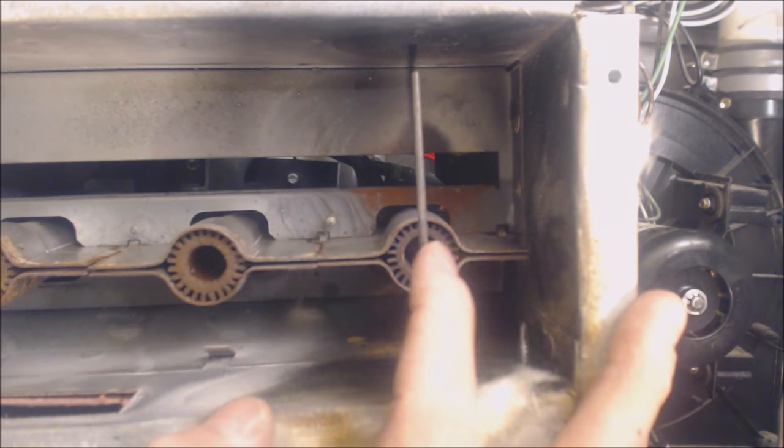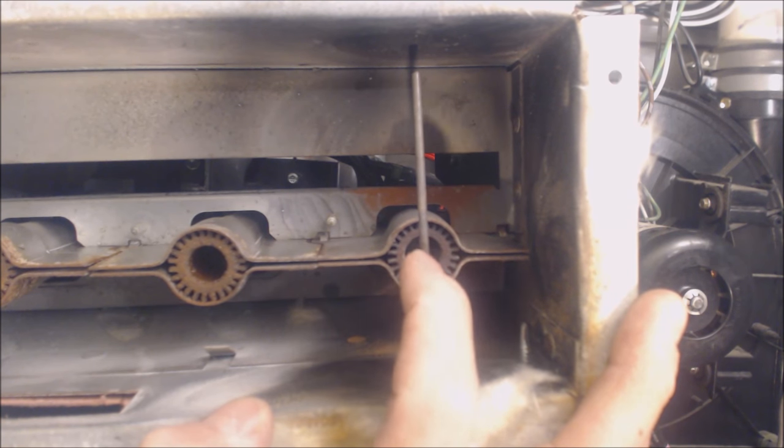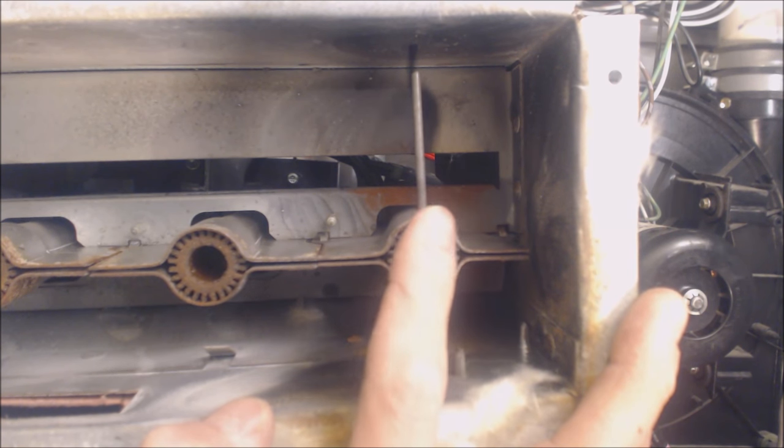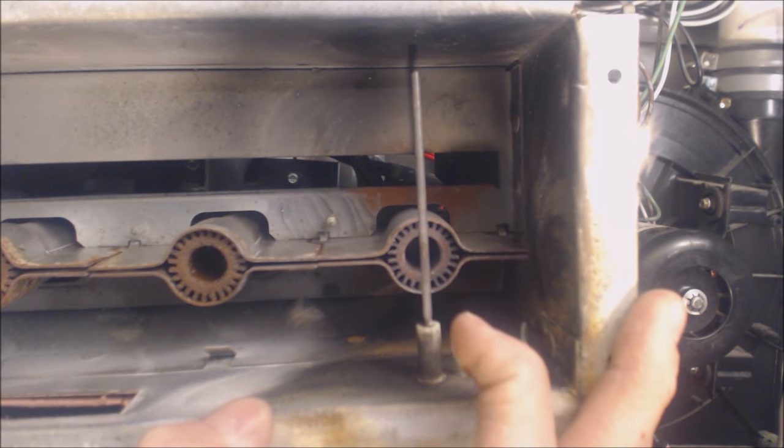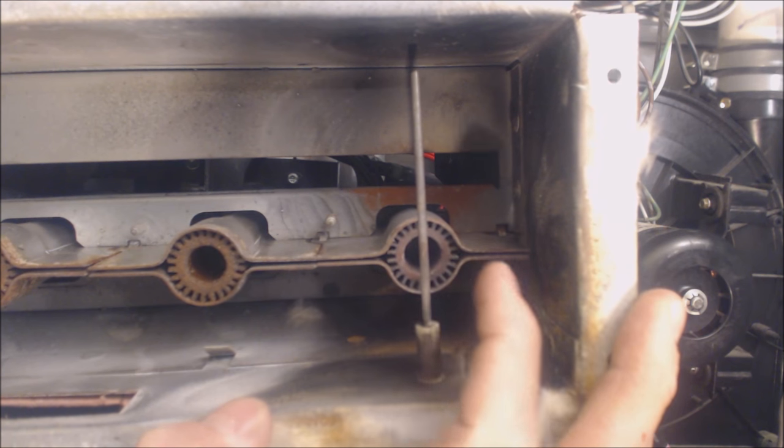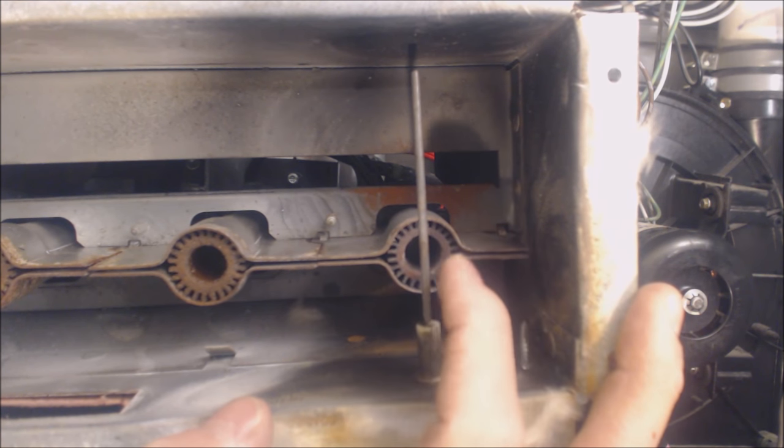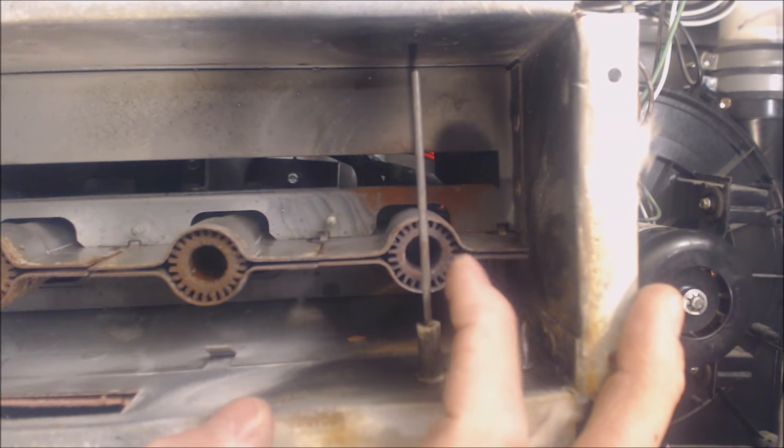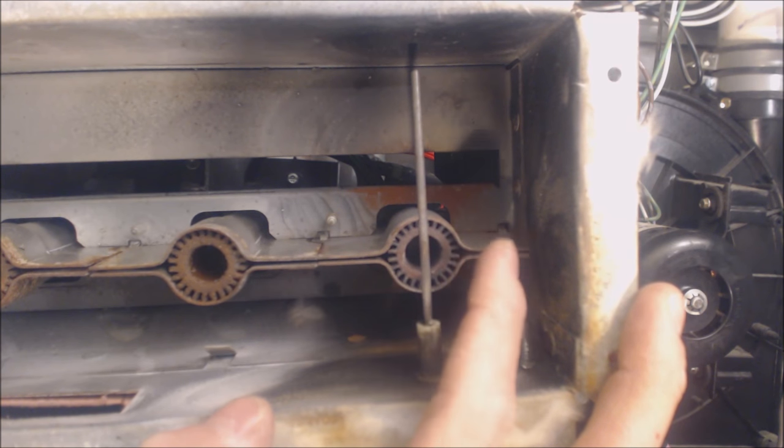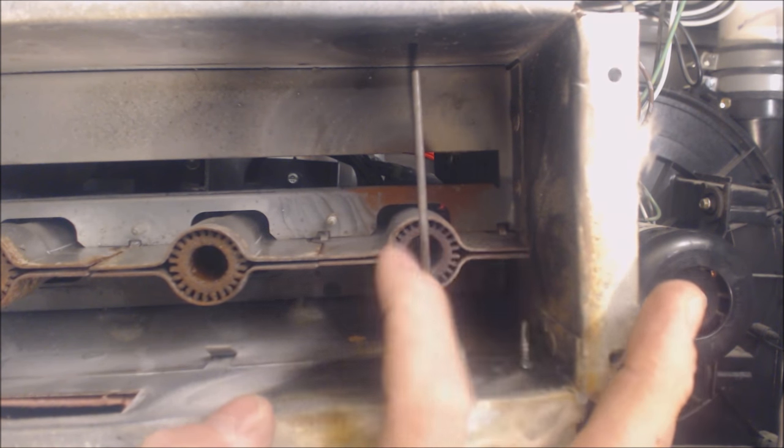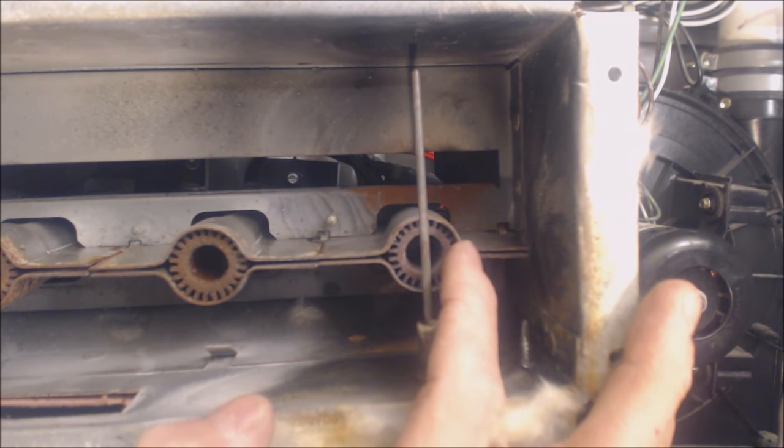So what happens is 90 to 110 volts goes through the rod into the flame. It travels in the flame through the carbon that's in the flame while it's running and it's seeking out the larger surface area of metal.